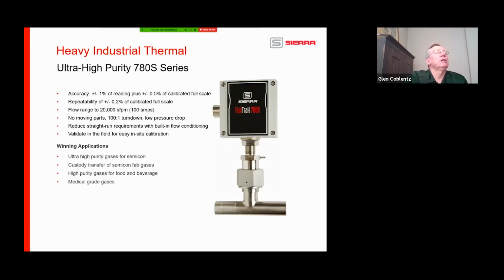780S UHP, again, watch those flow rates, watch those maximum flow rates per gas. They're all in that gas table in the price list. Different accuracy. And again, these are going to be for semiconductor applications. This has an RA finish on the inside of anywhere from 5 to 10.